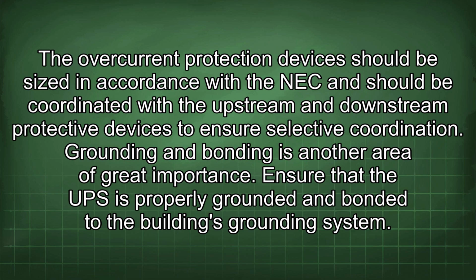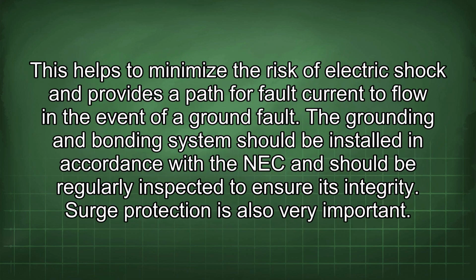Grounding and bonding is another area of great importance. Ensure that the UPS is properly grounded and bonded to the building's grounding system. This helps to minimize the risk of electric shock and provides a path for fault current to flow in the event of a ground fault. The grounding and bonding system should be installed in accordance with the NEC and should be regularly inspected to ensure its integrity. Surge protection is also very important.